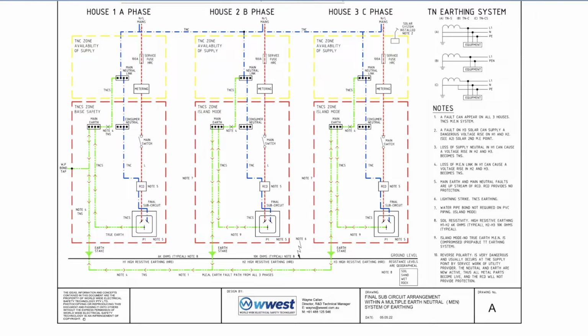And so here again we've got loss of the main M.E.N link in house 1 can cause a voltage rise in house 2 and house 3, and again it becomes a TNS earthing system, because why? See note 4, you've lost that link. And this can happen because of corrosion. There's lots of things that can affect the earth stake down here. You can whippersnip that off. The water pipe bond can come unattached. There's lots of things that can happen there. And one of the biggest problems that you have with this earthing system, the TNCS, is reverse polarity. And reverse polarity happens up this end of the architecture.